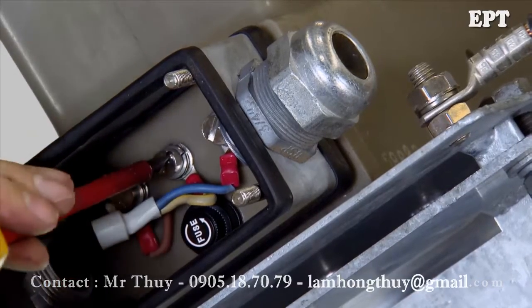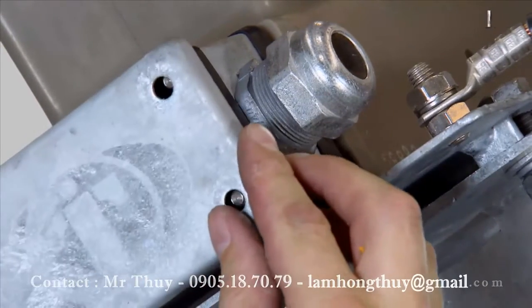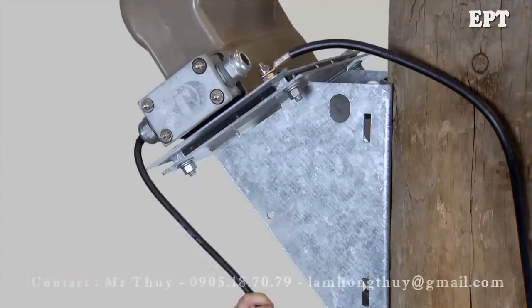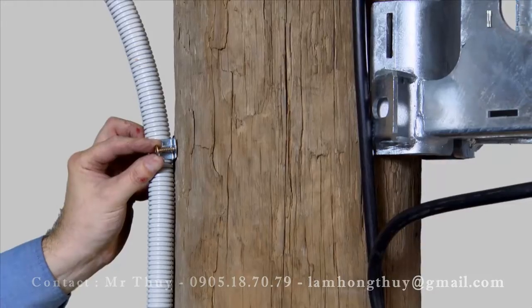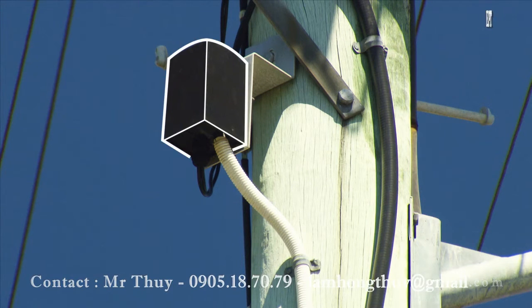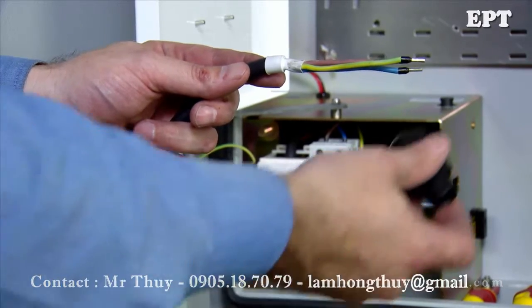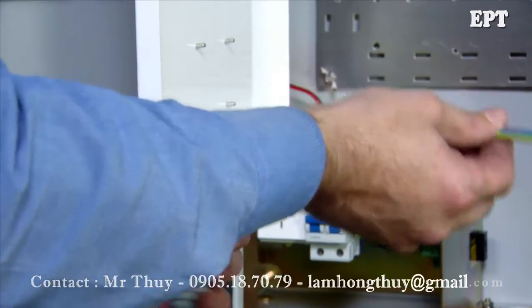Terminate the connections to the VT with proper sized lugs. Fit and secure the cover making sure the gasket is in place. It's recommended to have external protection for the cable. Secure the cable to the pole at regular intervals. A double pole isolation point is recommended so the RC10 can be isolated from the low voltage supply.